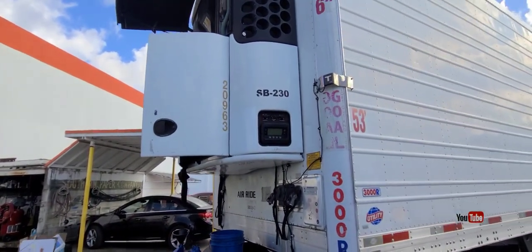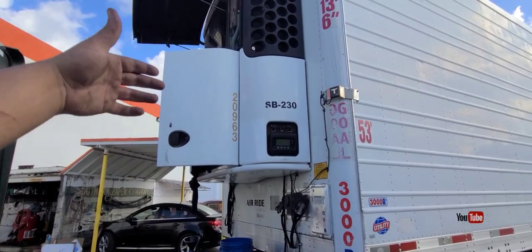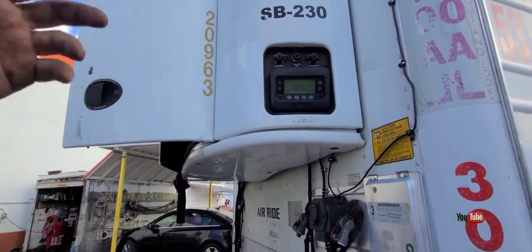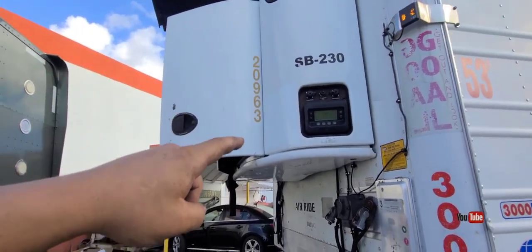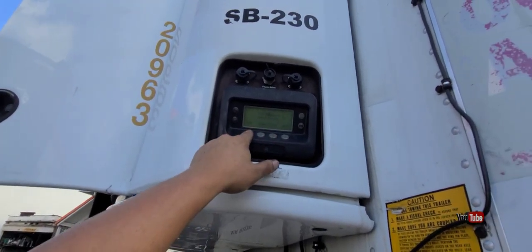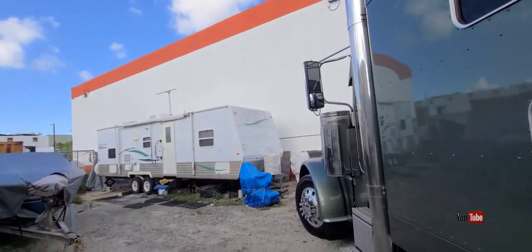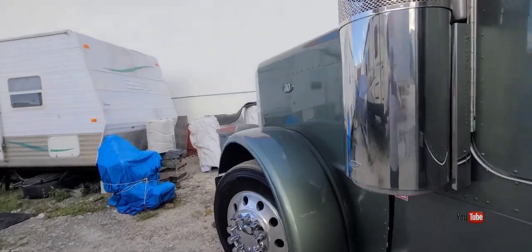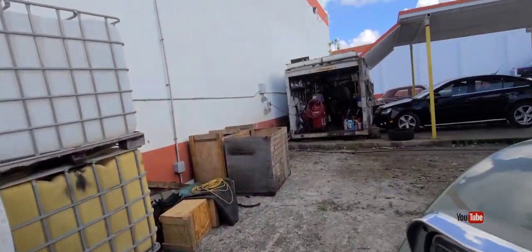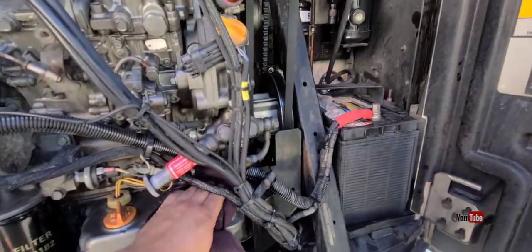See, there you go, same process. So now I have to redo the whole thing again. I have to cut it open, prime it again, and make sure that, see, alarm. Engine stop, yeah, we know that, all right. So let's turn it off for now. So we gotta do, like I said, the same thing again. We gotta prime it, the whole nine yards. You can do that process maybe 2 or 3 times with no issues at all. Something very normal. Okay, so I've done it several times.